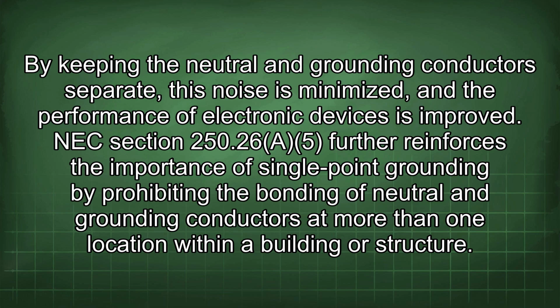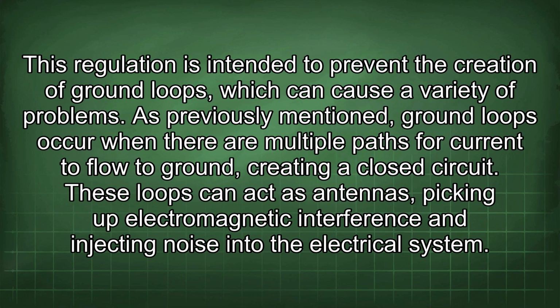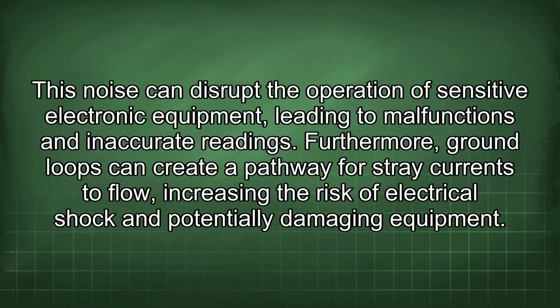NEC Section 250.26 further reinforces the importance of single-point grounding by prohibiting the bonding of neutral and grounding conductors at more than one location within a building or structure. This regulation is intended to prevent the creation of ground loops, which can cause a variety of problems. As previously mentioned, ground loops occur when there are multiple paths for current to flow to ground, creating a closed circuit. These loops can act as antennas, picking up electromagnetic interference and injecting noise into the electrical system. This noise can disrupt the operation of sensitive electronic equipment, leading to malfunctions and inaccurate readings.